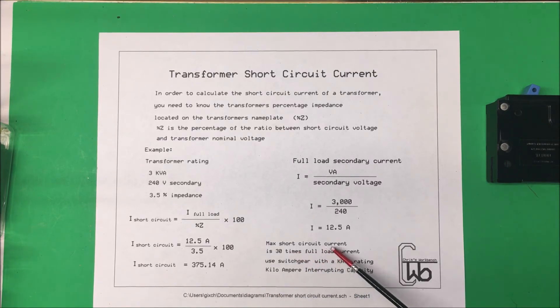So the max short circuit current is about 30 times the full load current. The switch gear has to be rated with a KAIC rating, that's kiloampere interrupting capacity, able to take this 375 amps.